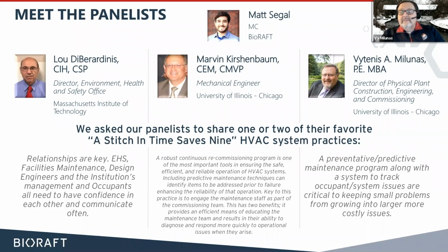I think, Marvin, you had some thoughts on that. Yeah, so we're trying to treat the entire space. Again, people got fixated on air changes per hour, which, again, I agree with Lou, they shouldn't. But look at the space, what ASHRAE would consider the conditioned or occupied space versus the entire volume. So where do you apply that air change rate number? What volume do you use? If we use the entire volume of the space, these numbers get very, very large. So again, I think there has to be some rethinking if we're going to design buildings to deal with some of these contagion issues, and look at how we distribute air and how we define ventilation rates in these spaces.